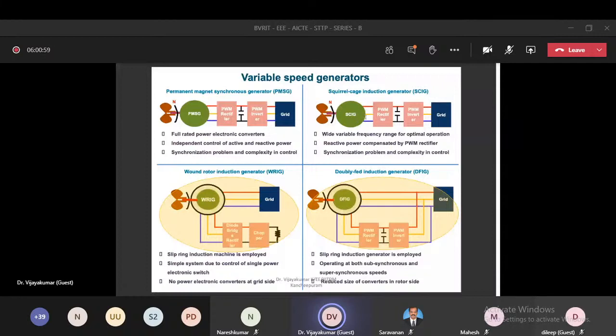If it's a grid, the frequency is 50 hertz. So for a 4-pole machine, 1500 RPM is the synchronous speed, right? But here you have the converter. By changing the switching angle of this converter, you can change the frequency at the stator terminals. If your frequency is 40 hertz, then what will happen? Your synchronous speed will come down. So at slow speed also, you can generate, even at 1000. If you are increasing to 40 hertz, so what is your synchronous speed?